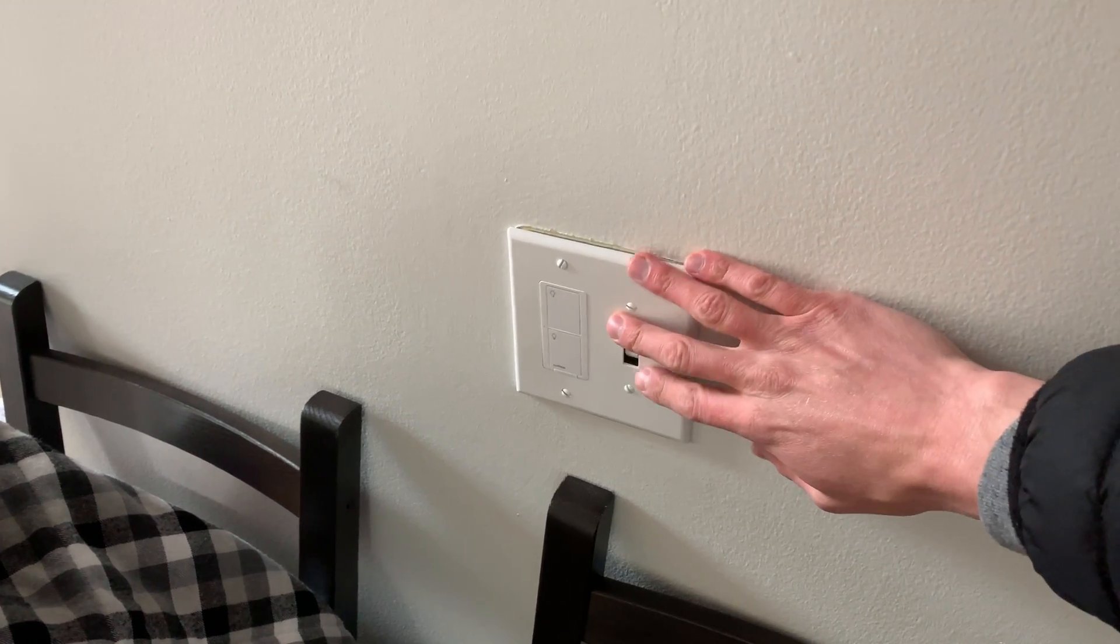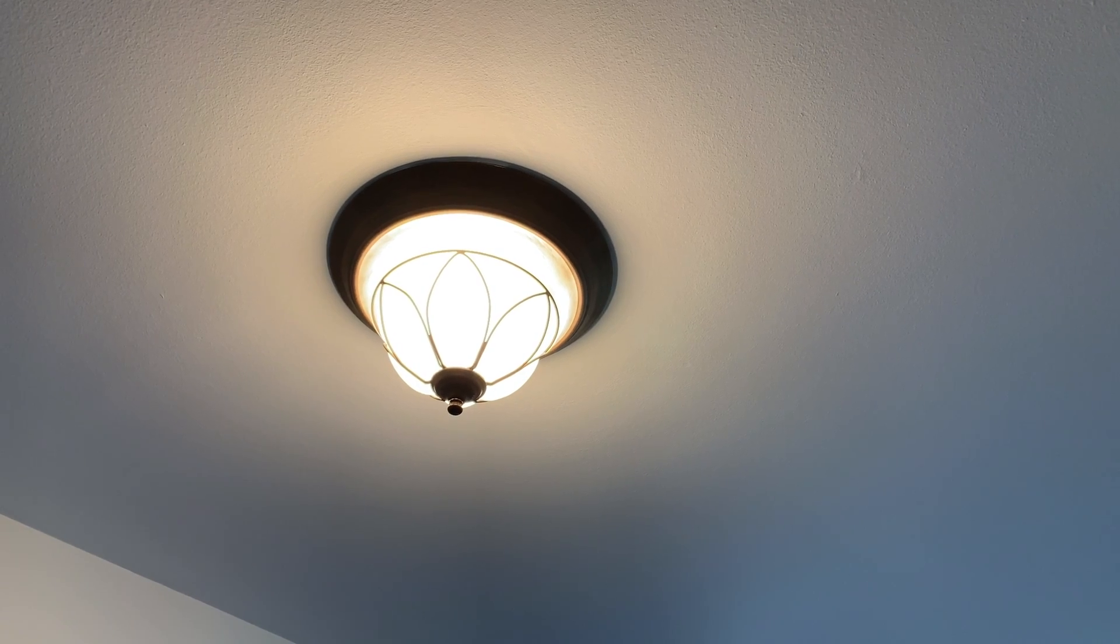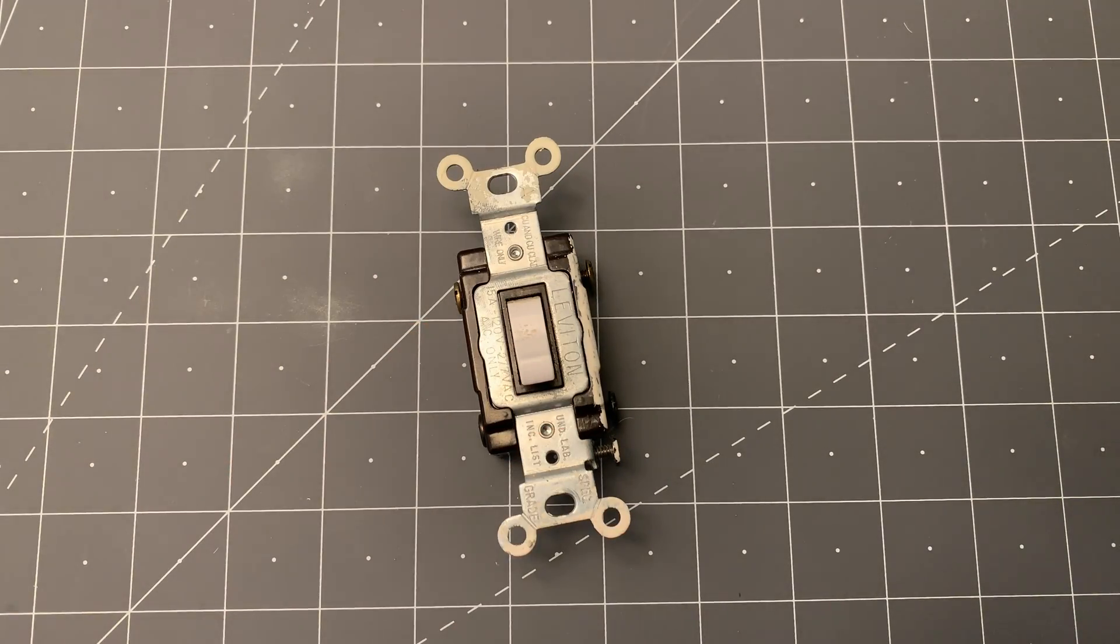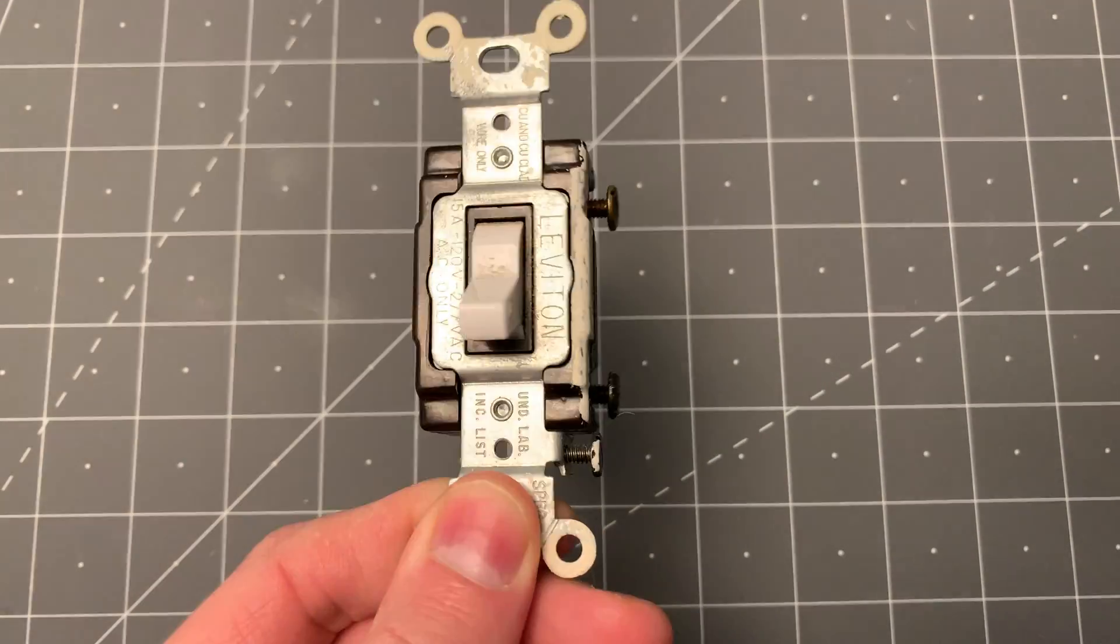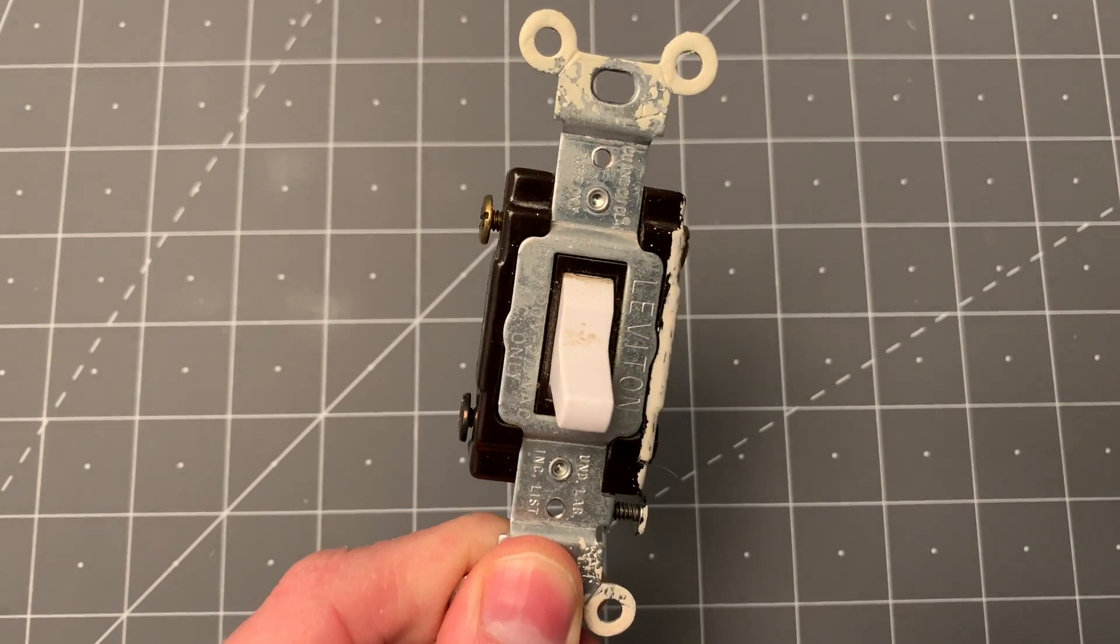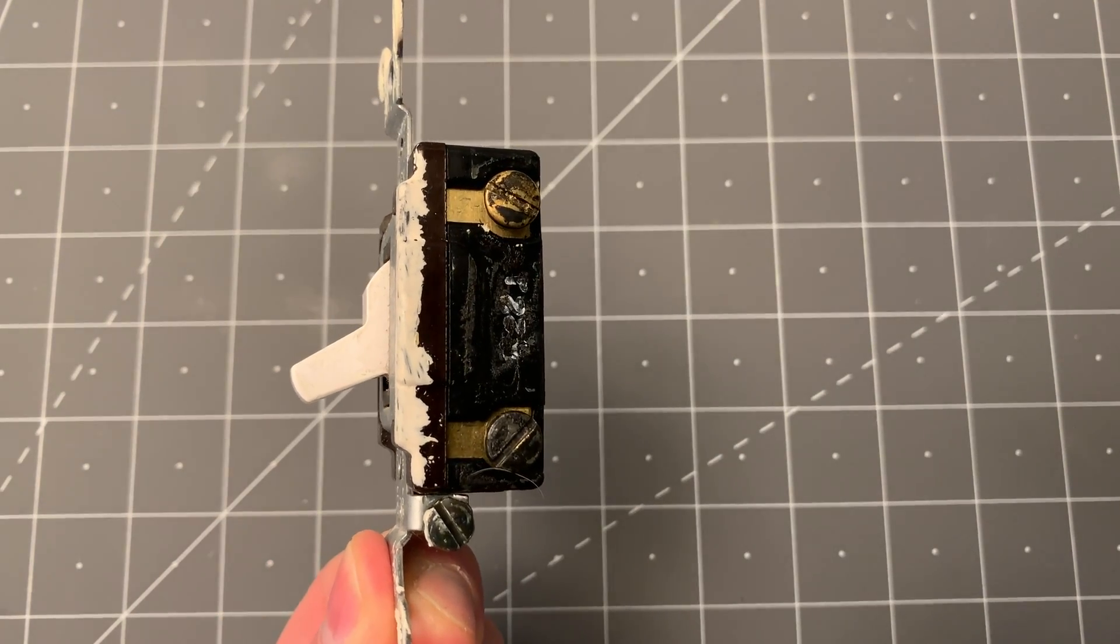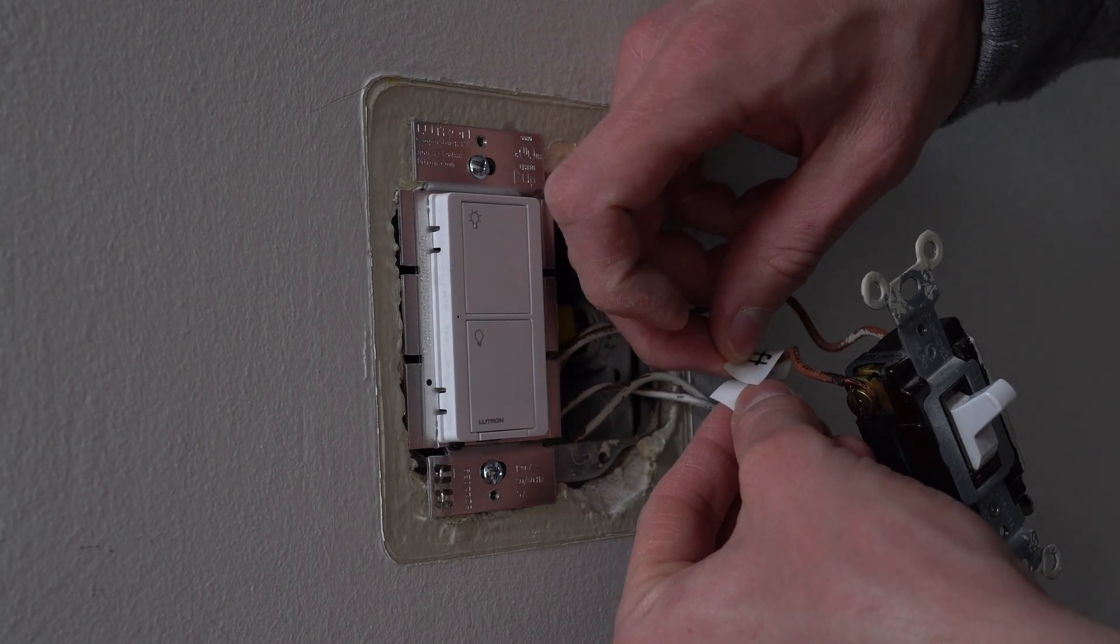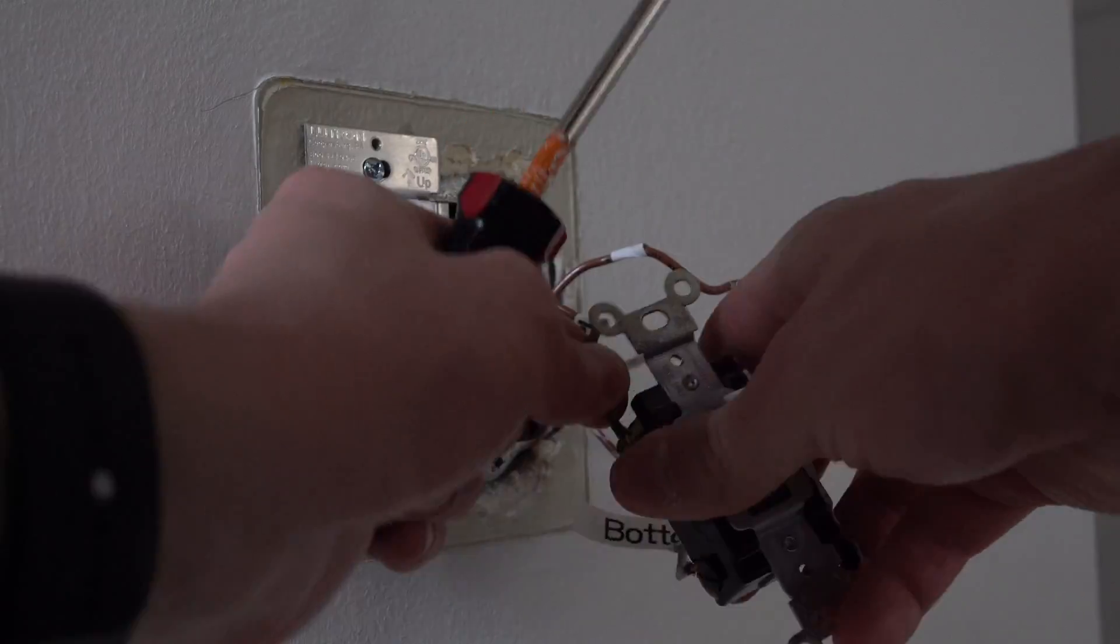And now it's time to merge the four-way switch into one controllable thing for the dimmer switch. Now, if you look at a typical four-way switch, you'll see two different colored screws. And oftentimes there'll be one color on the top two and then one color on the bottom two. And you don't really need to fully understand where each of those are going in the four-way circuit, but it's key that you know which screws they're screwed into. So I would recommend going through before you do this in case you ever need to or want to undo this label, which is the top left, the top right, the bottom left, the bottom right. And that way, if you ever get a basic four-way switch again, or maybe someday there's a smart four-way switch, you can swap it in easily by knowing the positions of those wires.